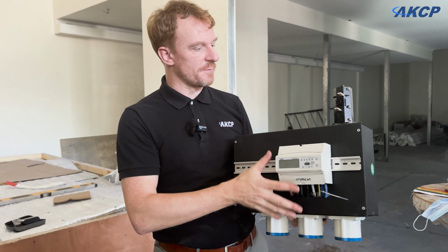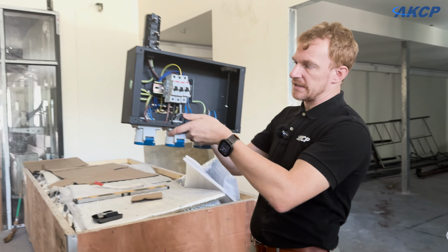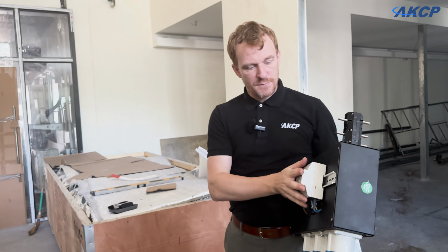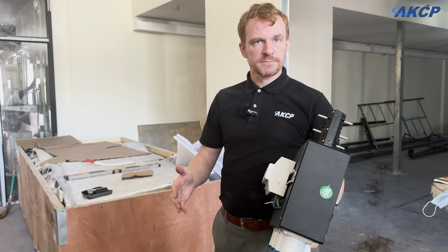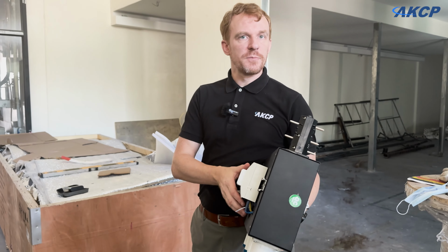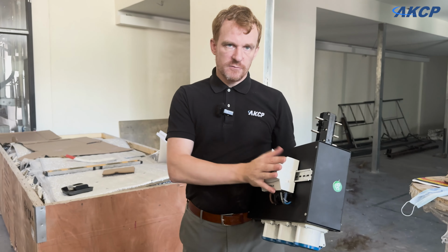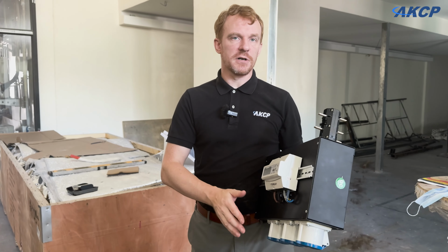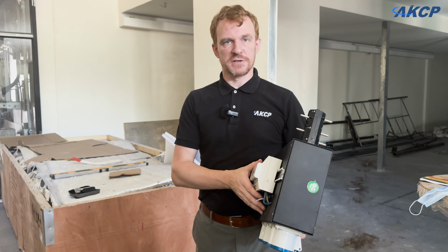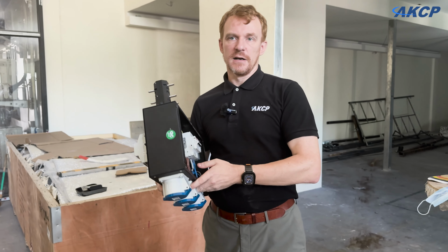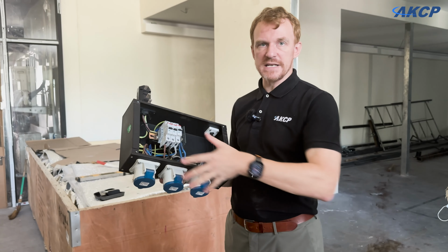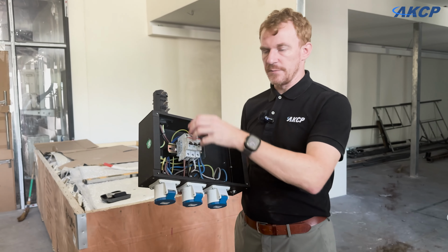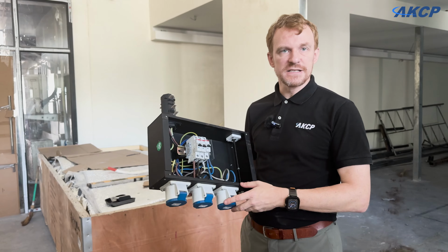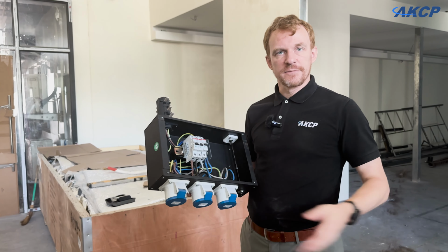So that'll be mounted on the back of these, and one of these then will sit above each one of the racks. So we have power metering on every rack, which allows us to then do PUE calculations, because we have the IT load power, and then we have other power meters which will be monitoring the facilities load. So that's basically how our electrical system is set up and how we're generating the heat in this test data center.